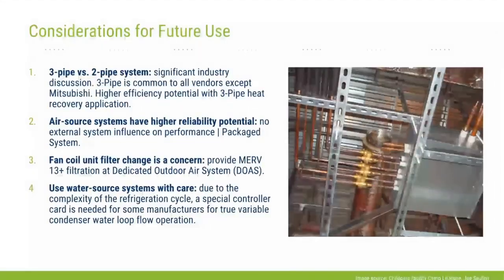So just some considerations for future use. We did end up using a 2-pipe system on this project, while 3-pipe is common to most other vendors other than Mitsubishi. There is potentially higher efficiency potential when you're really utilizing the heat recovery application for these systems with a 3-pipe configuration.